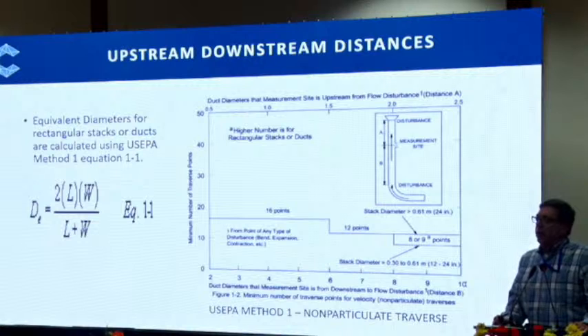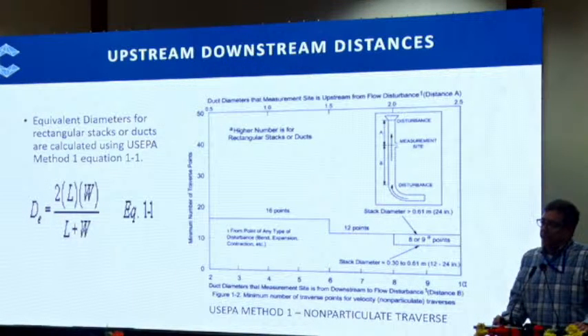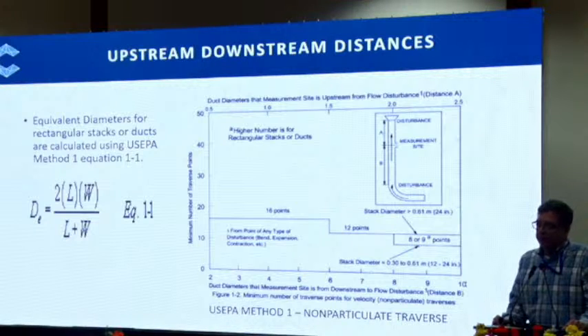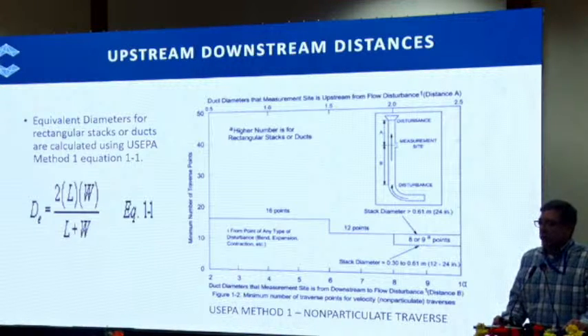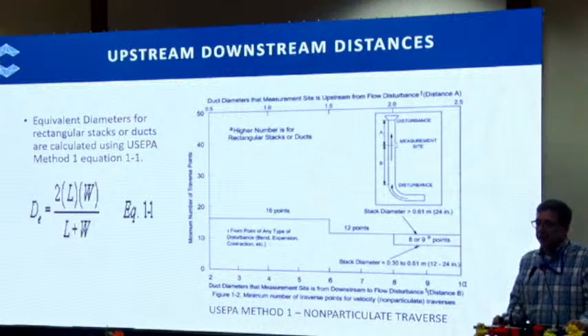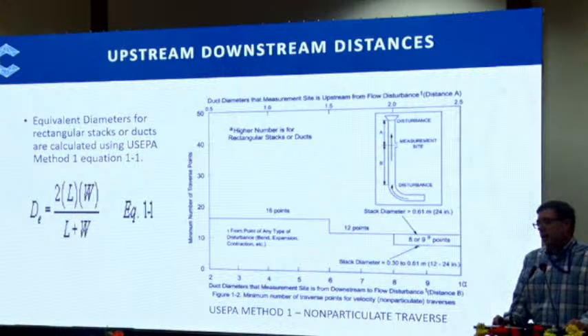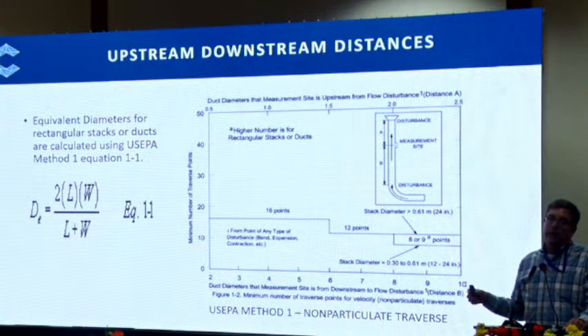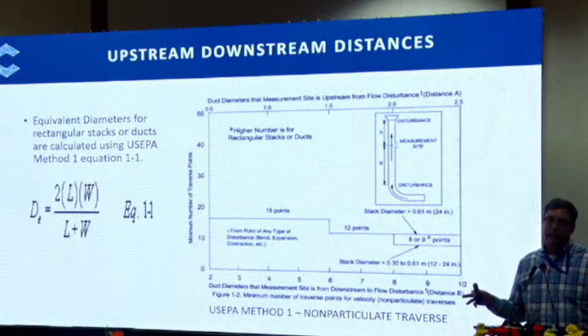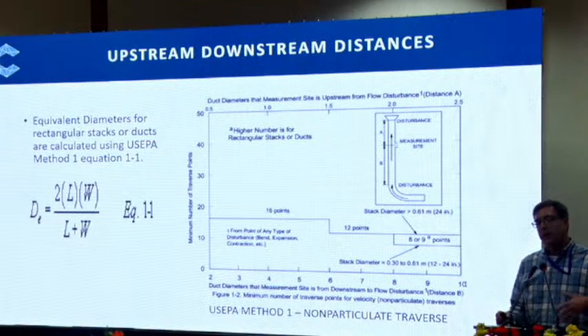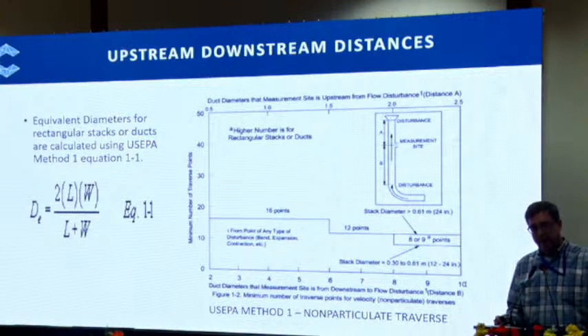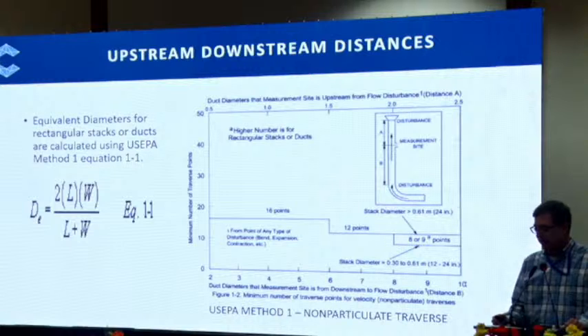So this is an EPA chart that shows you an ideal non-particulate traverse point selection. And this gives you the equation for the equivalent diameter calculation for rectangular ducts according to US EPA Method 1. So you can use these in conjunction to find the ideal point or ideal location. If you have enough run to do it, then you would find a laminar, in theory, a laminar position to test from.